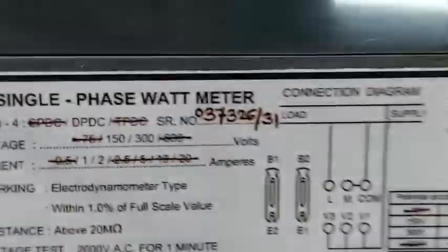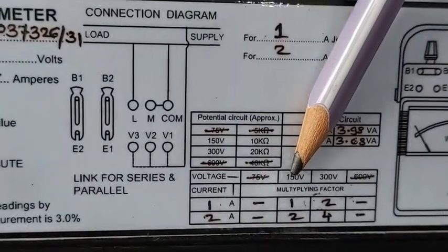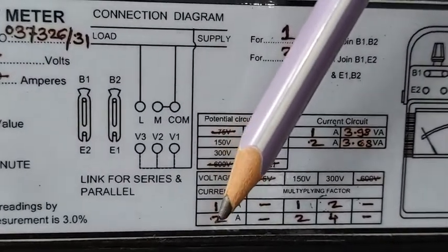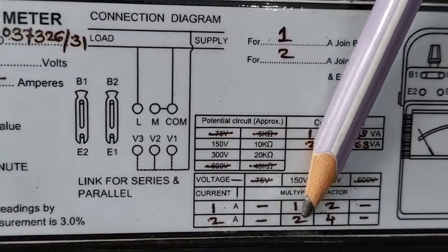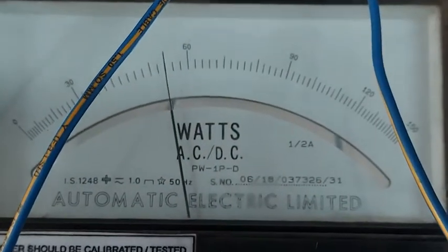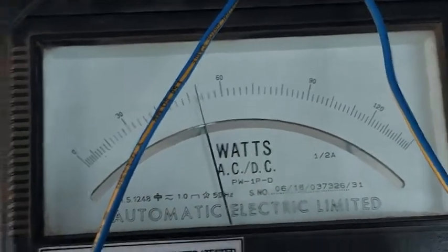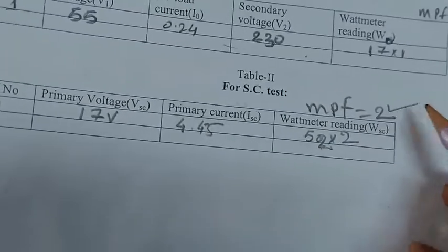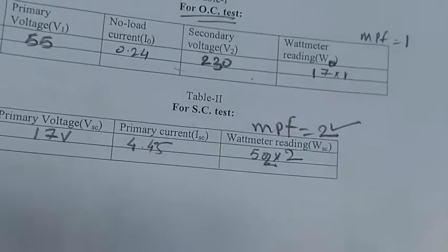And we have also already mentioned that the wattmeter voltage rating is connected to the 150 range. Here we can see, and from that we can get the voltage rating. So for 2 ampere and 150 volt, the multiplying factor is 2. Whatever reading is obtained here, that wattage must be multiplied by 2 so that we get the actual power consumed by the transformer in the short circuit condition. So we will write 52 multiplied by 2. The wattmeter multiplying factor is 2, that's why the reading is 52 multiplied by 2. This is the total consumed power.